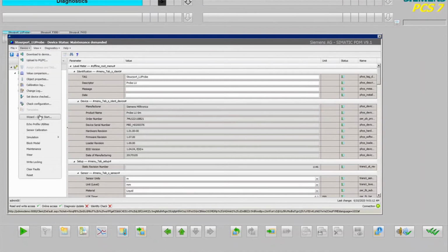Okay, if I selected a milliamp output device, you would have an option here to do loop test, which is a nice feature. So you want to see that you've got the right data going somewhere else. But with a Profibus device, what I can do is simulate. So I can simulate the Profibus value. I want to make physically sure that on my DCS, that is the right value going to the right tag on my DCS. So you can do that. So it's not necessarily called a loop test on Profibus PA, but it's sort of doing the same thing.